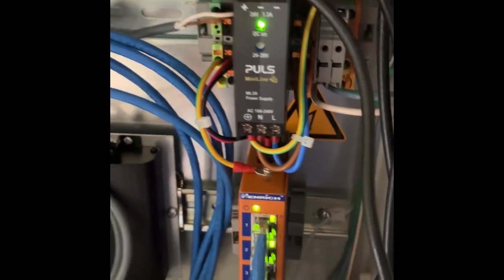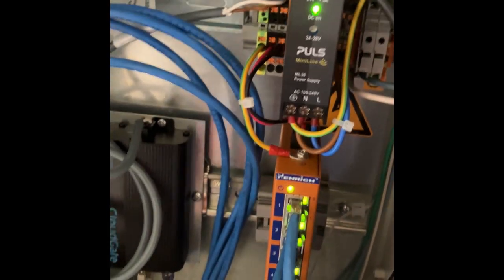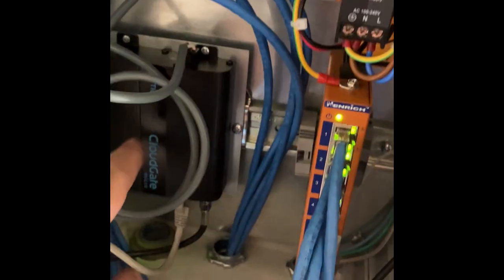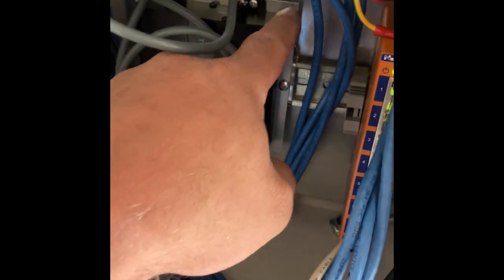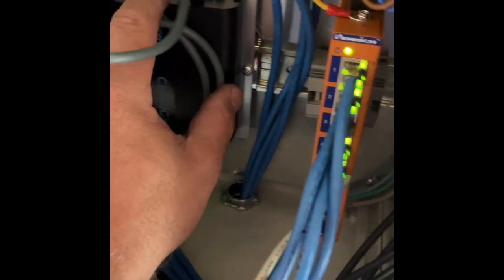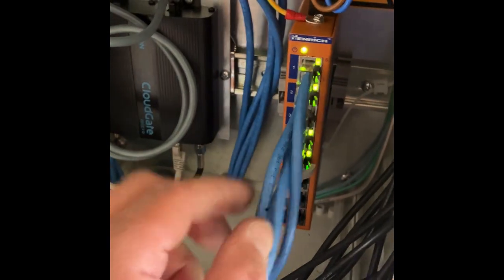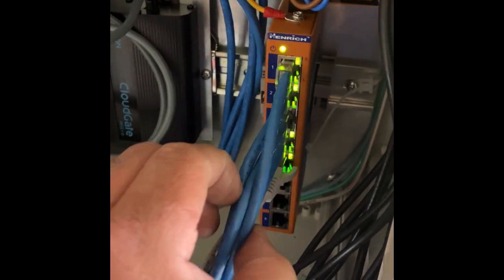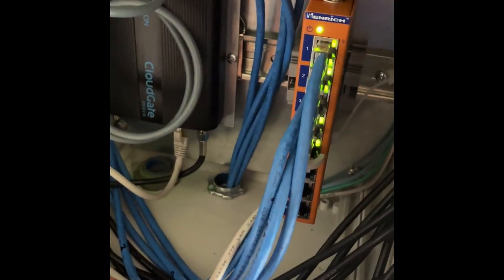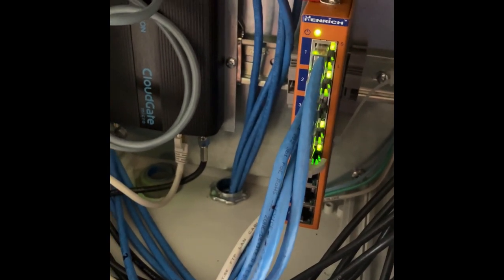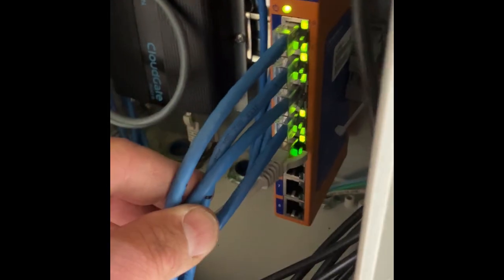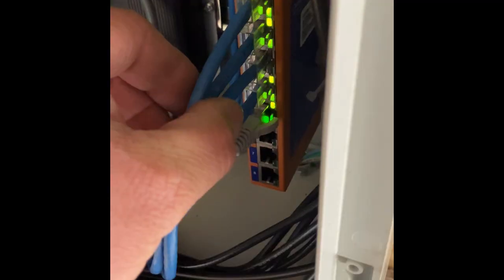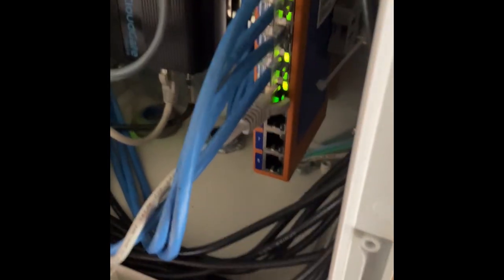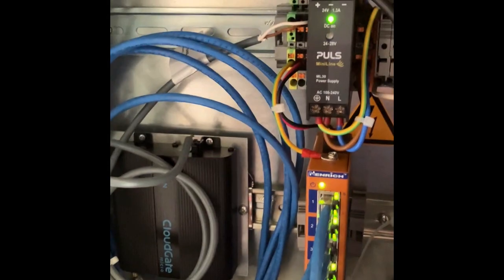All you've got to do is have your electrician hook in the 120 right there, and then you'll wire in your 24 volt DC power to the gateway, mount the gateway to this little back plate, and put it on the DIN rail and all that. Your electrician or whoever should have an Ethernet cable ran from each compressor, and one more going over to the Aero panel itself. It doesn't matter what configuration the plug goes into on the switch, whatever suits you. You'll have your patch cable from the switch to the gateway, and that's it. It all comes in one nice little spot here.